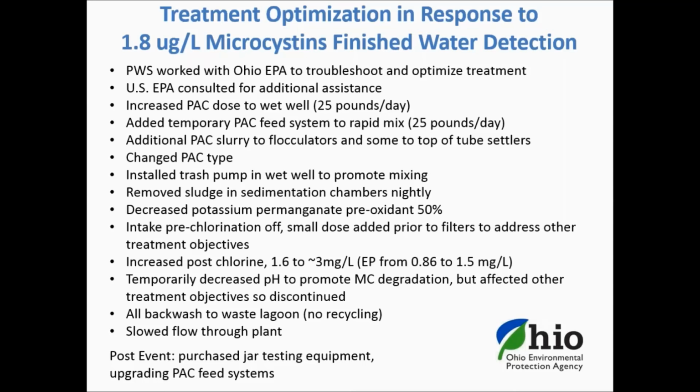Thankfully, our systems are truly wonderful, and most would do about anything to help out their fellow public water systems. So this water system not only provided carbon, but delivered it immediately via the superintendent's personal truck, which involved a ferry crossing to the island. That type of camaraderie is wonderful and shows the benefit of building relationships prior to a crisis. Another quick fix was installing a trash pump into the wet well to promote improved mixing. Prior to installing the pump, we observed that the carbon just slid down the side of the wet well, sinking to the bottom and forming a sludge. After the pump was added, the whole basin turned gray, visually demonstrating improved mixing.